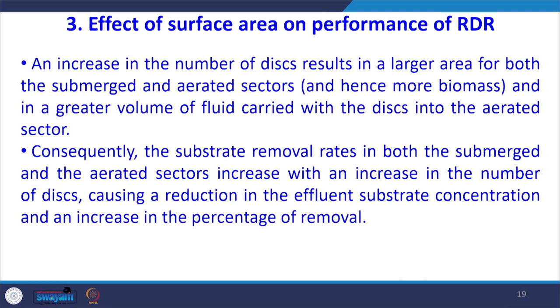The effect of surface area on performance of RDRs: an increase in the number of discs results in a larger area for both the submerged and aerated sectors. Hence, more biomass can be grown and a greater volume of fluid can be carried into the aerated sector. Consequently, substrate removal rates in both sectors increase, causing a reduction in effluent substrate concentration and an increase in percentage removal. Higher surface area directly correlates with better performance.